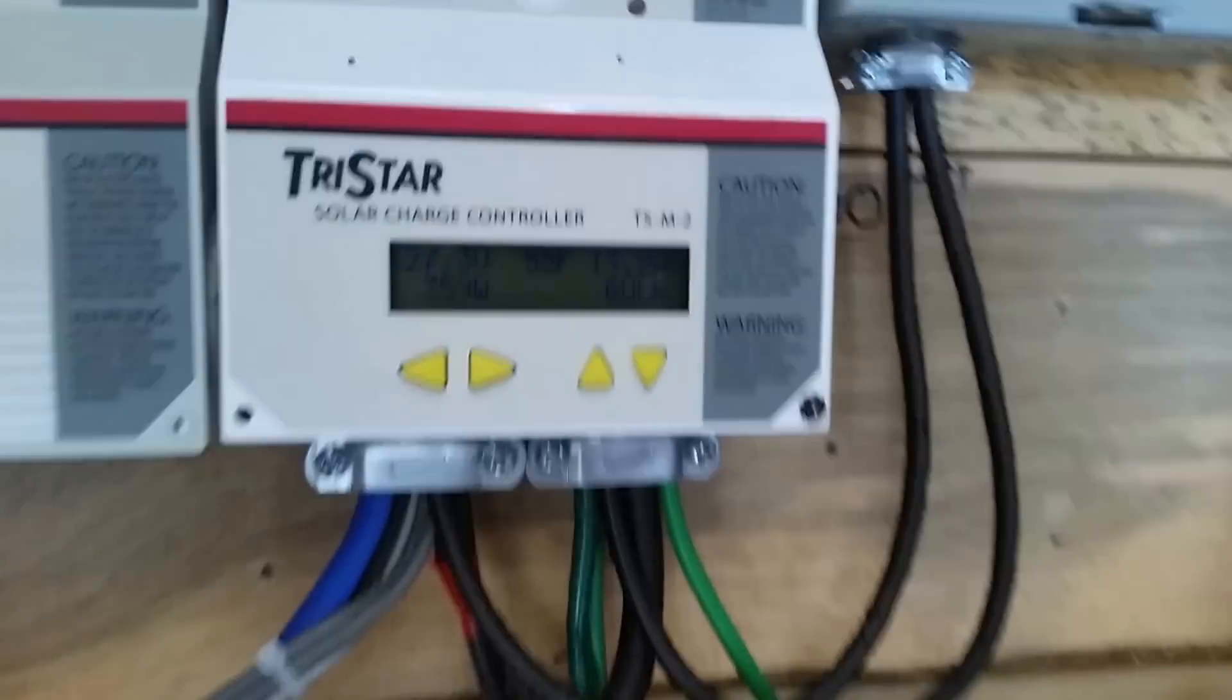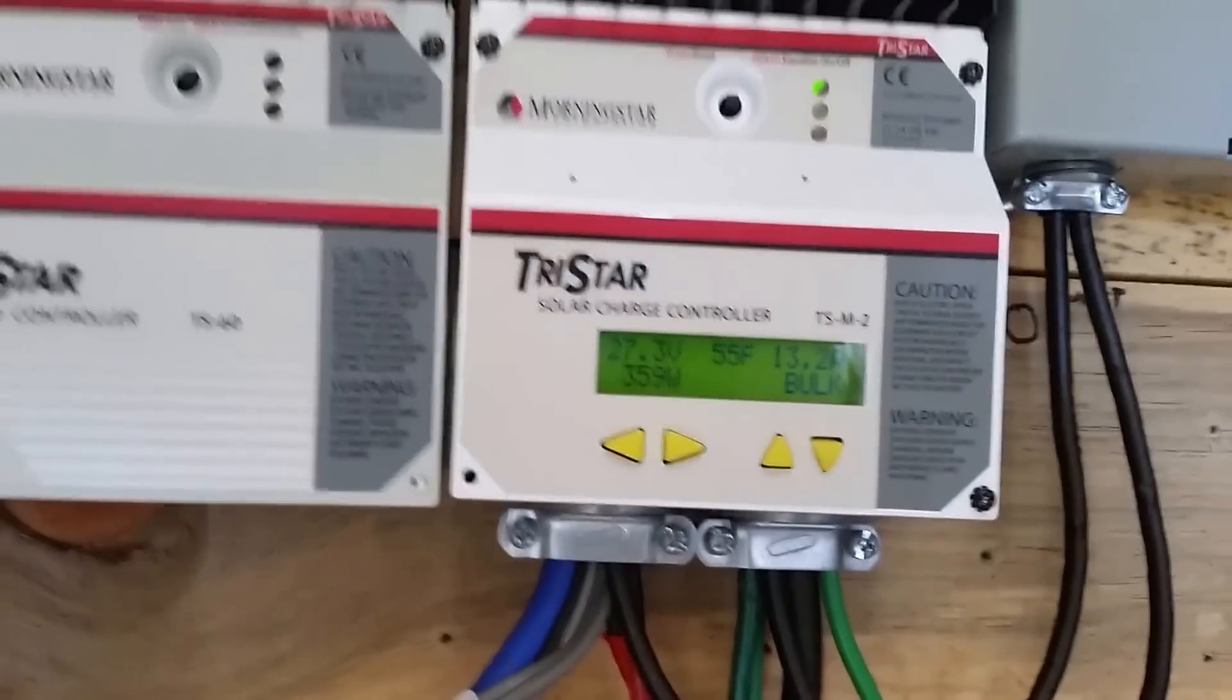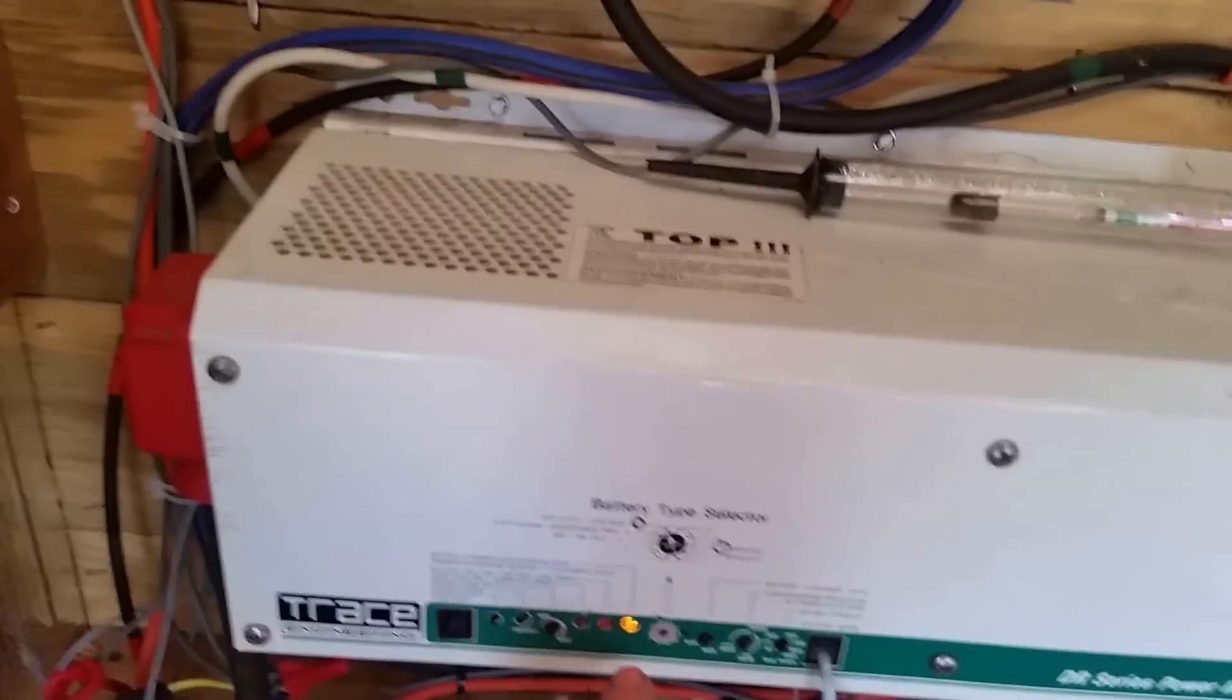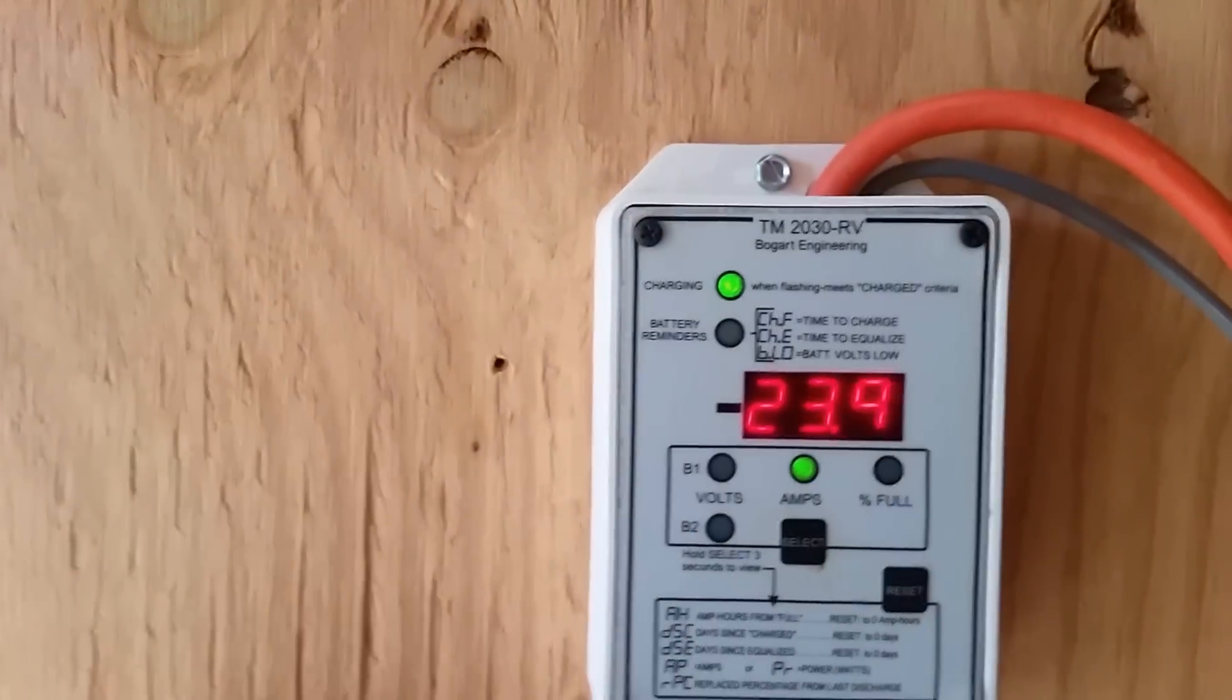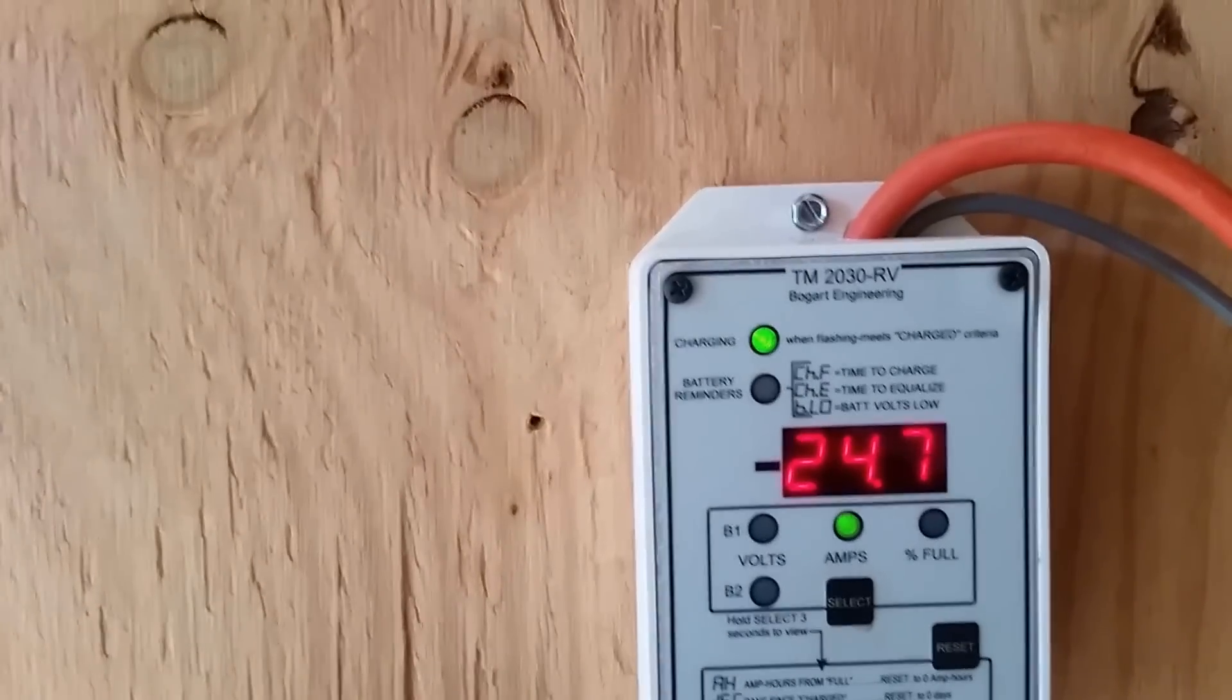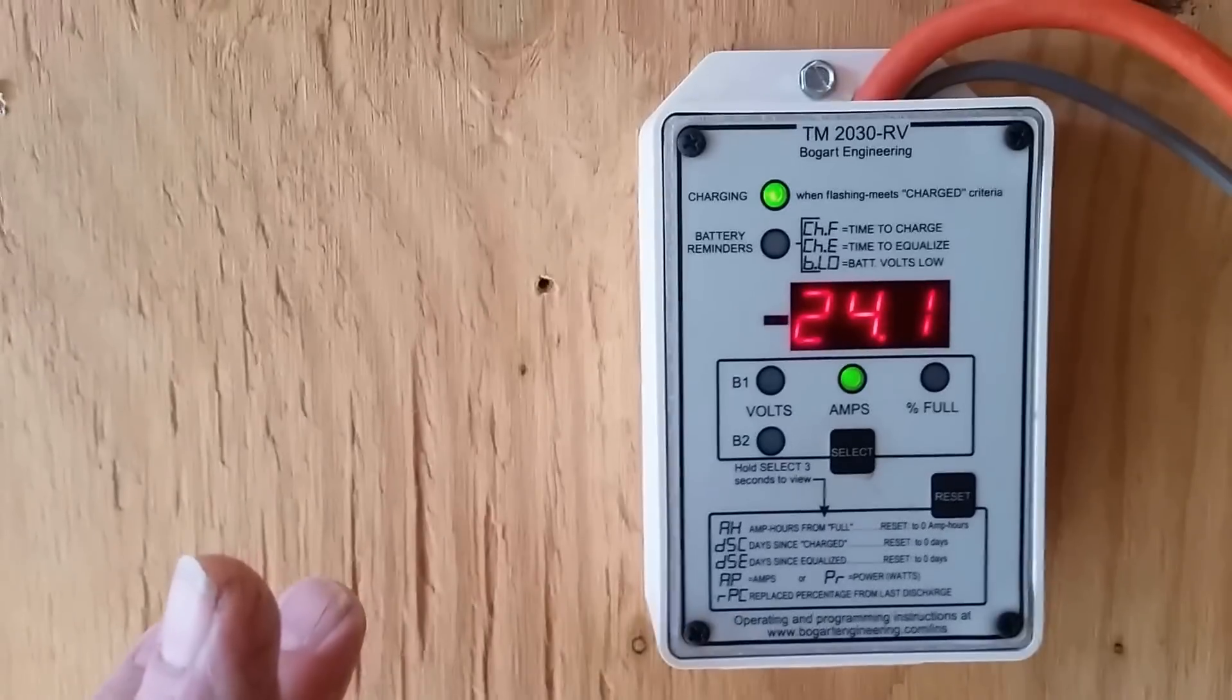Here we see I've got 13 amps coming in from solar. I'm in bulk mode. The battery should be calling for bulk. The inverter charger is showing I'm in bulk mode and I should be getting 70 amps to the battery from the charger plus the 13 from solar. So I should be getting 83 amps right now and I'm only getting 24.